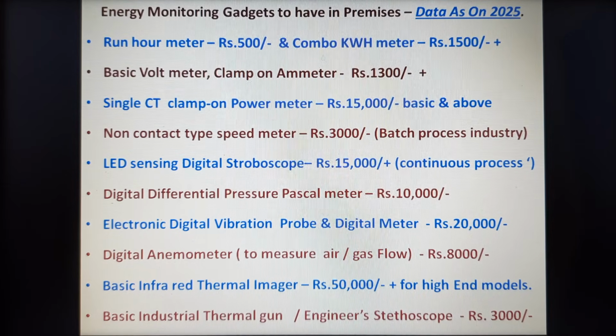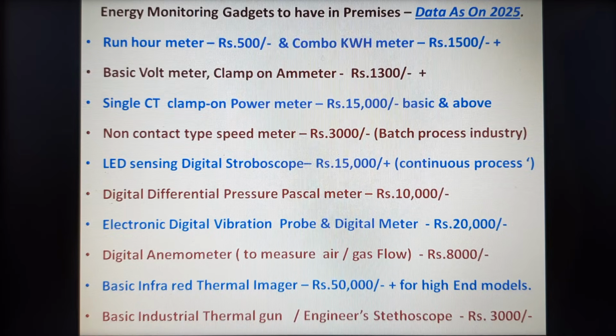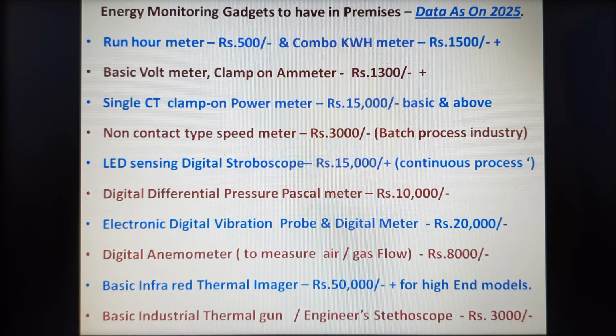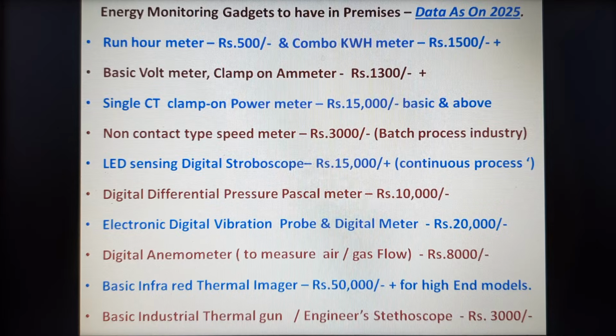See what is the blower delivered Pascal, what is the Pascal demanded by the process. Both need to be checked as such. Then comes the next stage, predictive monitoring: electronic digital vibration probe and digital meter. Wherever the motors have a lot of vibrations, it just costs only 20,000, but definitely you can see the vibration amplitude and the acceleration due to gravity, whether we are within the norms or whether it is above.